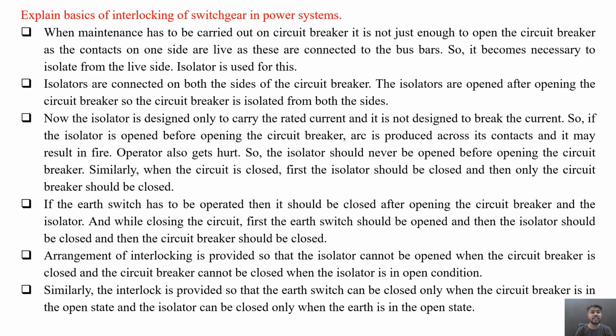If the earth switch has to be operated, then it should be closed after the opening of the circuit breaker and the isolator. And while closing the circuit, first the earth switch should be opened and then the isolator should be closed and then the circuit breaker should be closed. Arrangement of interlocking is provided so that the isolator cannot be opened when the circuit breaker is closed and the circuit breaker cannot be closed when the isolator is in open condition.